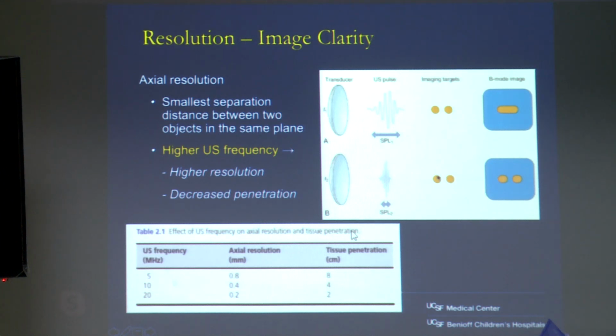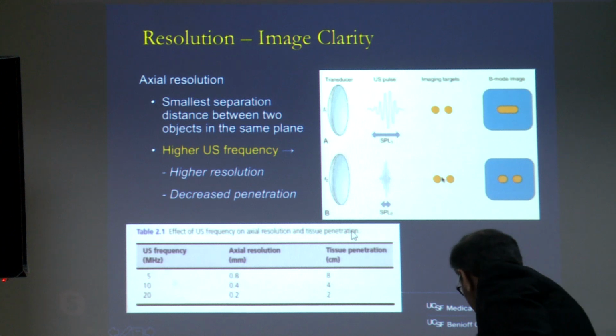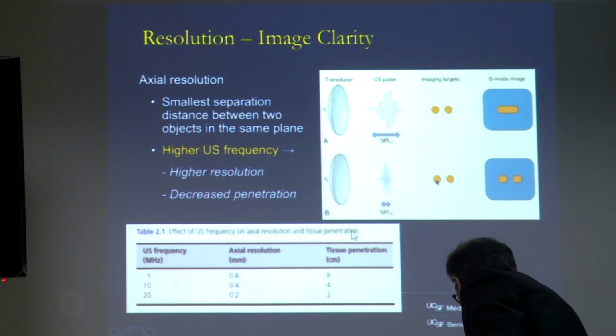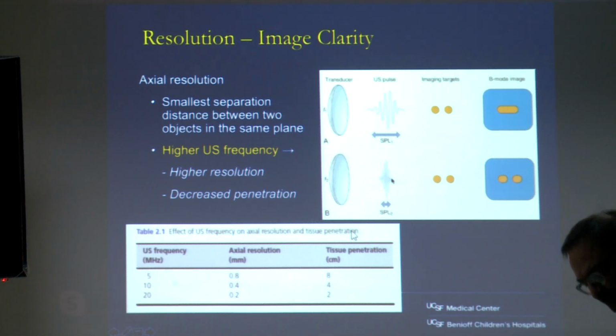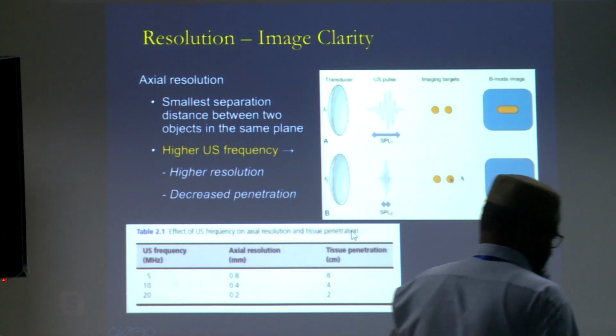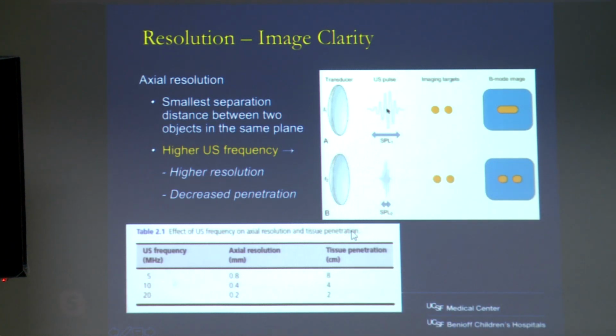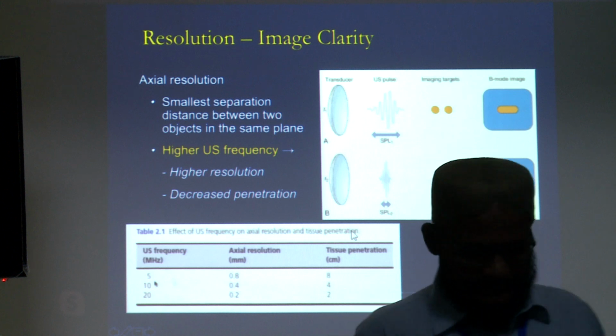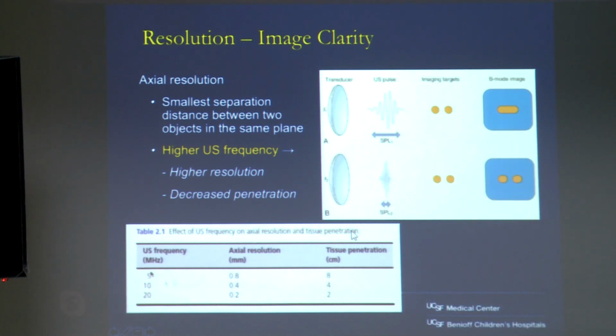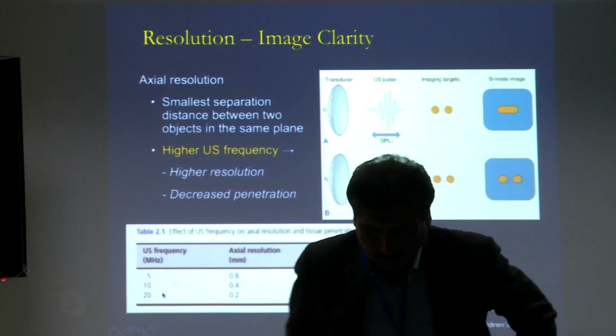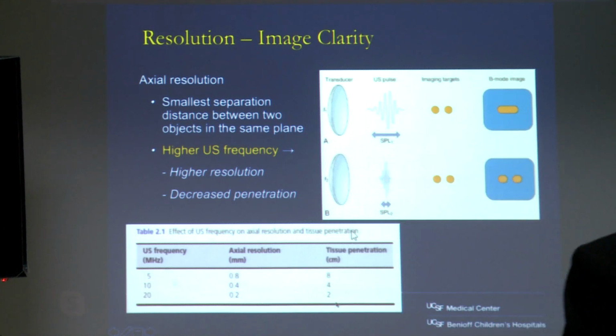On the other hand, it's inversely proportional to the depth of evaluation. The higher the frequency, you can imagine that they are stronger waves, but they lose their energy quickly, so you can't go very deep. Whereas at a lower frequency, they're not as energetic and they can go deeper. This table summarizes it. At a frequency of 5 megahertz, you can penetrate up to 8 centimeters, whereas at a frequency of 20 megahertz, you can only go up to, say, 2 to 3 centimeters.